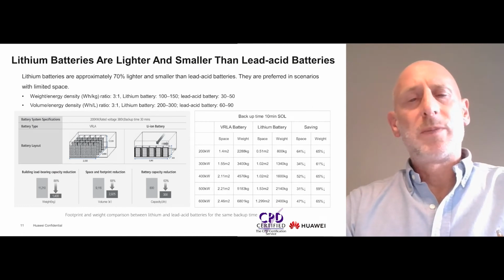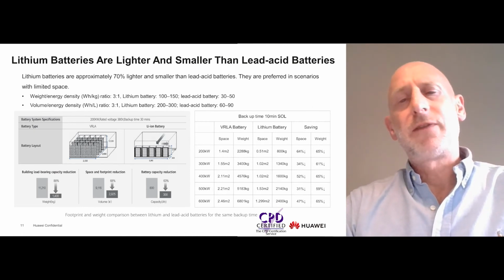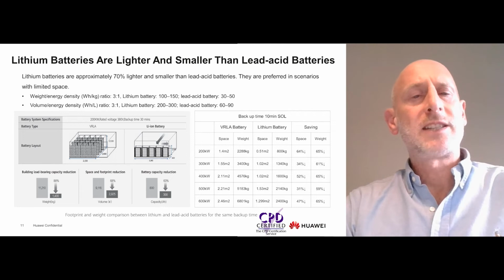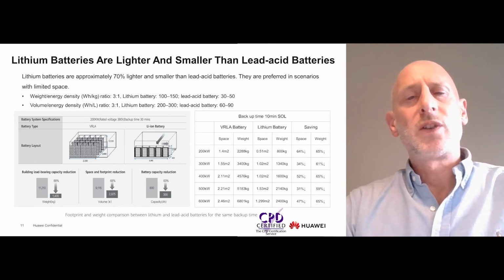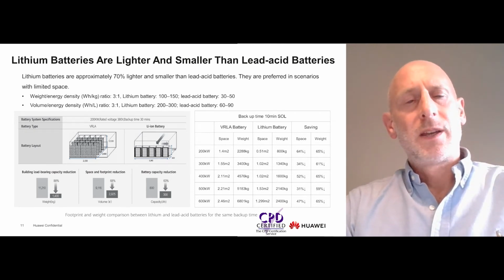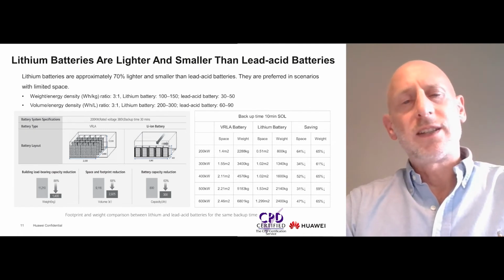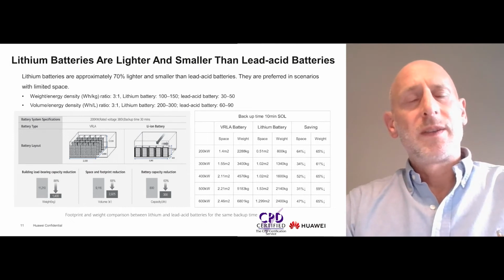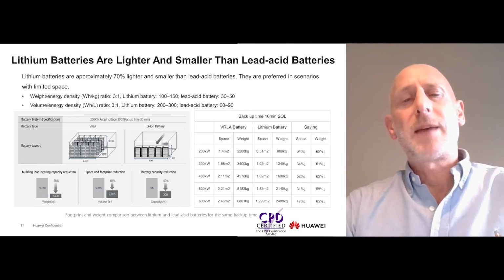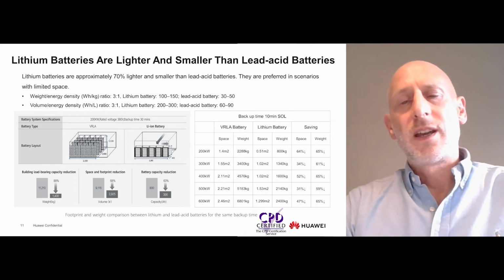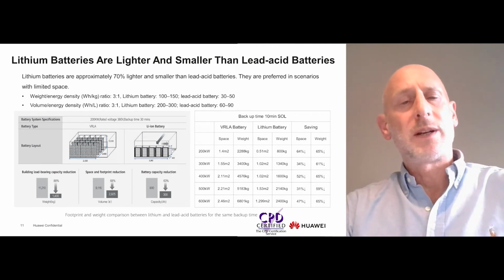Lithium battery-powered UPS systems can reduce footprint by 50 to 70% compared to lead-acid batteries, supporting scenarios with limited space. When considering lithium and lead-acid batteries' weight-energy density, there is a ratio of approximately 3 to 1. This is similar to the volume-to-energy density, with a similar ratio of 3 to 1. Thanks to the higher power density of lithium batteries, the overall solution has a smaller footprint.